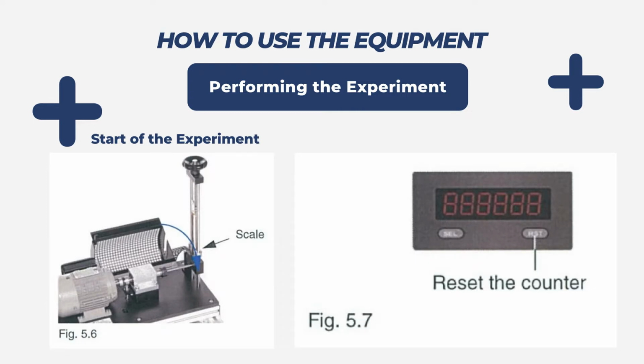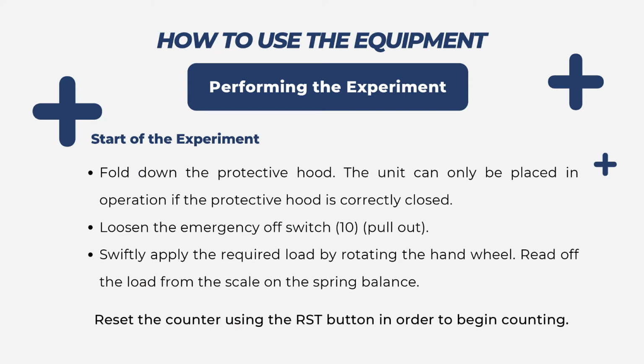How to use the fatigue testing machine in performing the experiment. To start the experiment, pull down the protective hood. The unit can only be placed in operation if the protective hood is correctly closed. Loosen the emergency off switch. Swiftly apply the required load by rotating the hand wheel. Read off the load from the scale on the spring balance. Reset the counter using the RST button in order to begin counting.